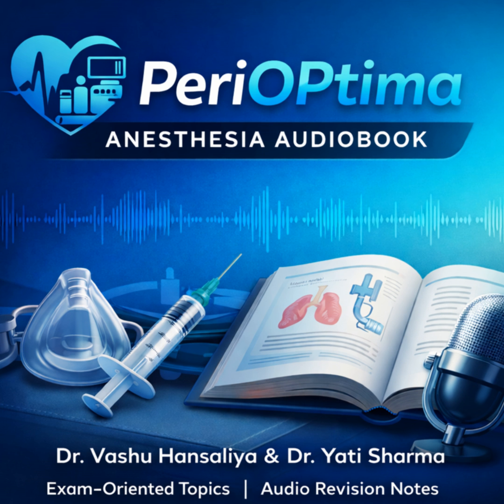Got it. Now the lockout interval, this is the safety net we talked about. Yes, the definition is crucial. The mandatory time period after a successful bolus during which the pump will not deliver another dose, even if the button is pressed. And what's the standard time for that? Both Miller and Stoelting recommend 5 to 10 minutes. Why 5 to 10? Why not 2 minutes? Or why not 20? This is a classic viva question. What is the scientific basis for the lockout interval? And the answer is the time to peak effect.